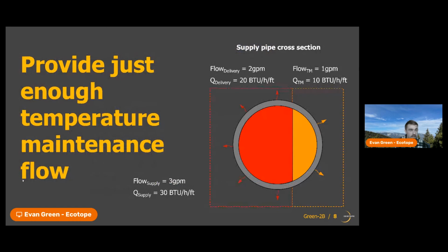So our main goal, like I mentioned, is to get domestic hot water to the occupant and get it there hot. And in order to do that, we'll need to make sure that the water doesn't spend too much time in those pipes and cool down to a point where it's no longer acceptable to the occupant. And to do that, we'll have to make sure it's flowing quickly enough, meaning we have this minimum flow rate that we need to satisfy in order to maintain that hot water temperature. And just to make the numbers easy, we're going to assume that flow rate is 3 GPM. So if we're flowing 3 GPM to a specific fixture, that water will only cool down to, say, 115 degrees before it leaves the tap.